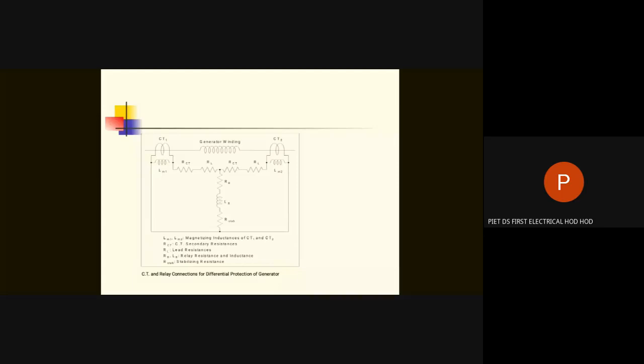LR, for the high impedance relaying. Such a kind of differential relaying is known as high impedance differential relaying, in which we connect a large resistance in series with the relay. So in such high impedance relaying, LR, the inductance of the relay, is usually so small that you can ignore it, right? So we will consider only RR, and R stab is intentionally connected in series with the relay to avoid mal-operation in case of external fault, as we have discussed, to avoid mal-operation due to CT saturation, mismatch due to non-identity of the two CTs, and the relay not being able to be connected at the exact midpoint. For that, we connect a large stabilizing resistance in series with the relay.